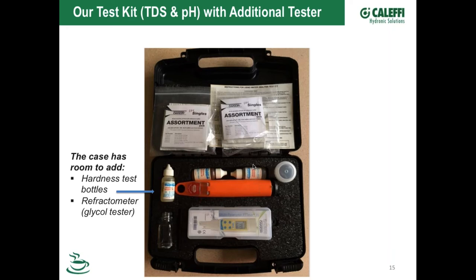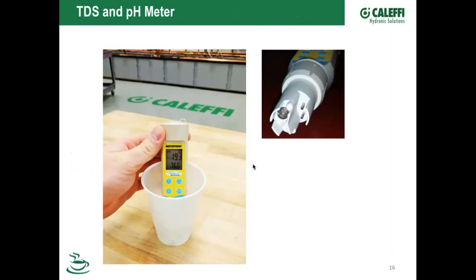If you know all the things that these meters are telling you, you're going to have a pretty trouble-free system. Again, you've got to go back every year or two and confirm that the water, those chemicals, or that glycol you put in are staying at the range you set.